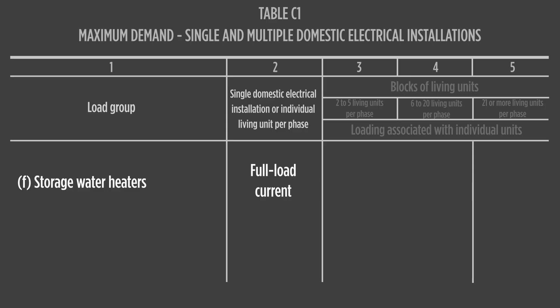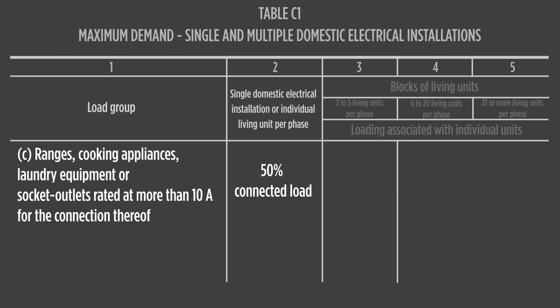Load groups C to M cover all other loads in a domestic installation, and it is the electrical worker's responsibility to place each load in the appropriate load group to calculate maximum demand. The current rating of any equipment installed will need to be determined so loading calculations can be made. Load group F is for storage hot water systems and allocates a full connected load for maximum demand calculation. Load group C, for cooking appliances and laundry equipment, allocates 50% of the connected load for maximum demand calculation. It is understood that these types of loads are not used continuously, and if full rating were to be applied, consumer main size would be unnecessarily large.